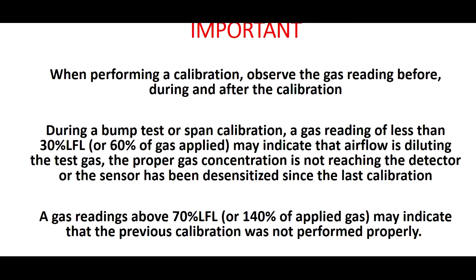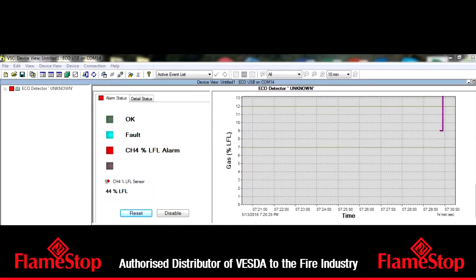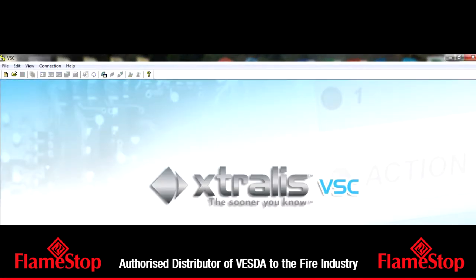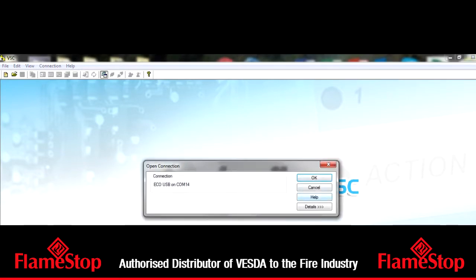A stable gas reading above 140% of the test gas concentration being applied may indicate that the previous calibration was not performed properly. Finally, you must generate a calibration report. To obtain the updated calibration report, you first must log out of the detector. Then, log back on.